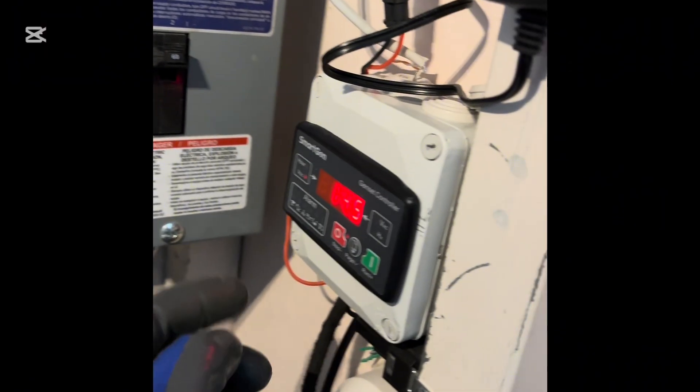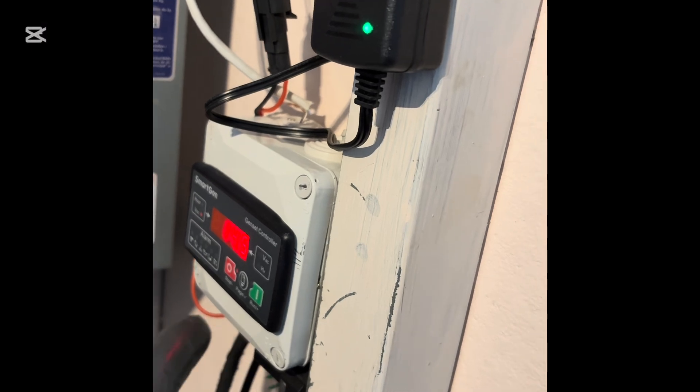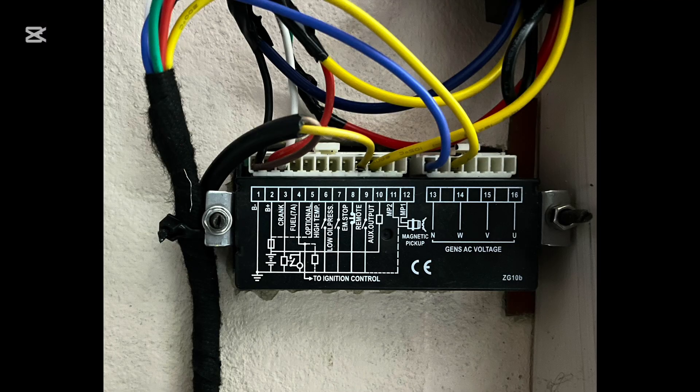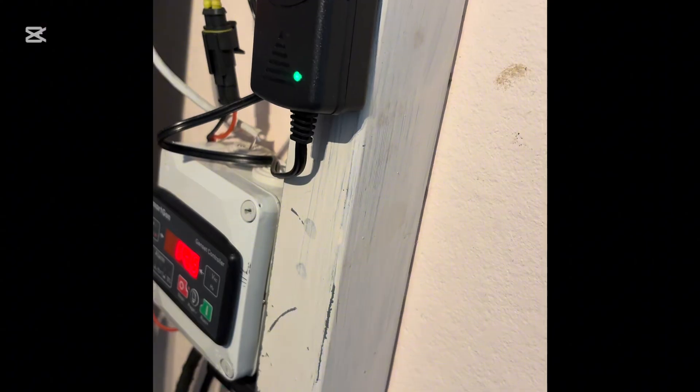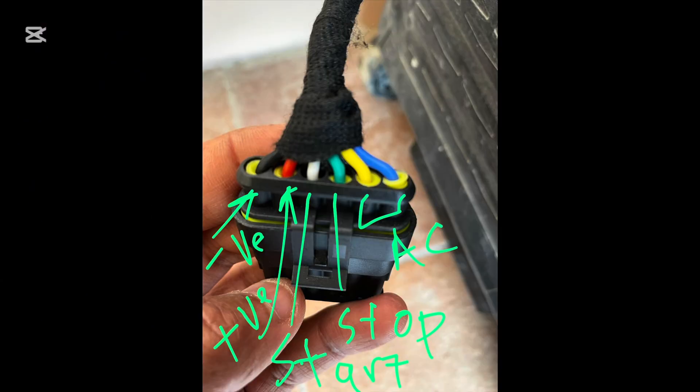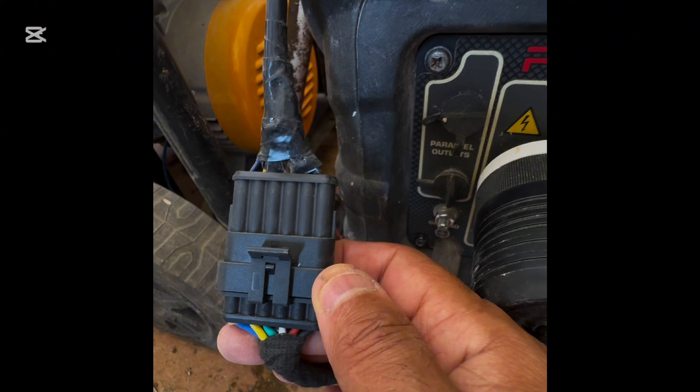To set up the generator controller you have six lines going from here to the generator. One line is the battery positive, battery negative, generator start signal or starter signal, kill switch signal, and then you have two feedback from the generator with 120 volt into the controller for the controller to know that the generator started. Those are the six terminals that come between the generator and the controller.